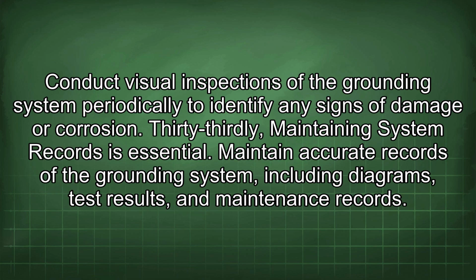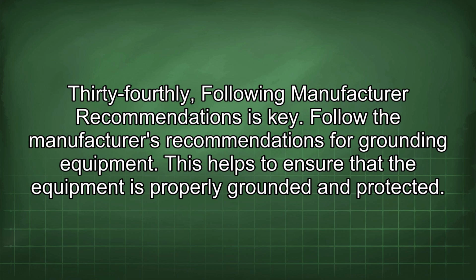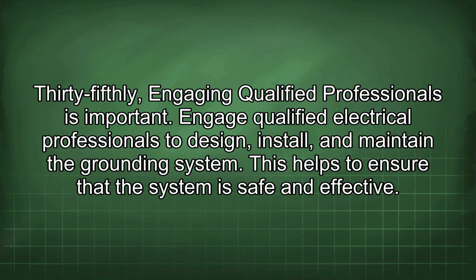Thirty-thirdly, maintaining system records is essential. Maintain accurate records of the grounding system, including diagrams, test results, and maintenance records. Thirty-fourthly, following manufacturer recommendations is key. Follow the manufacturer's recommendations for grounding equipment. This helps to ensure that the equipment is properly grounded and protected. Thirty-fifthly, engaging qualified professionals is important. Engage qualified electrical professionals to design, install, and maintain the grounding system. This helps to ensure that the system is safe and effective.